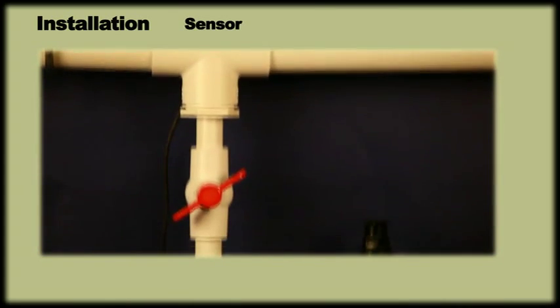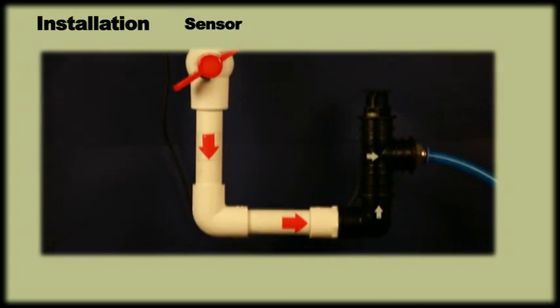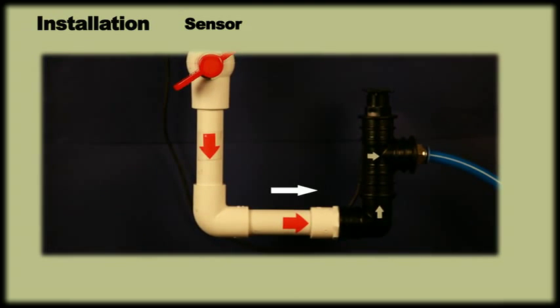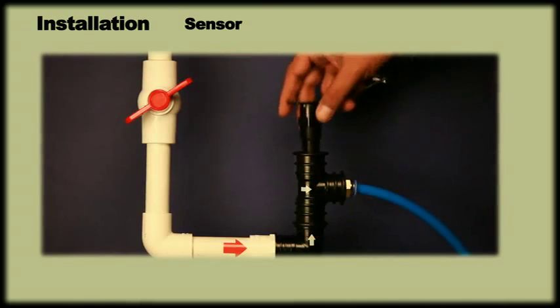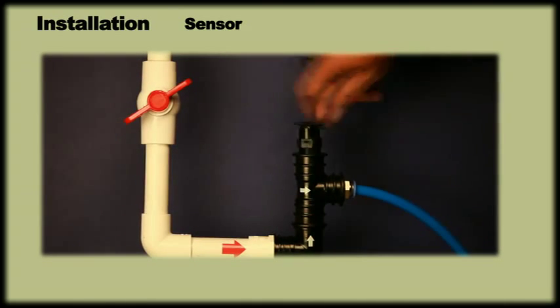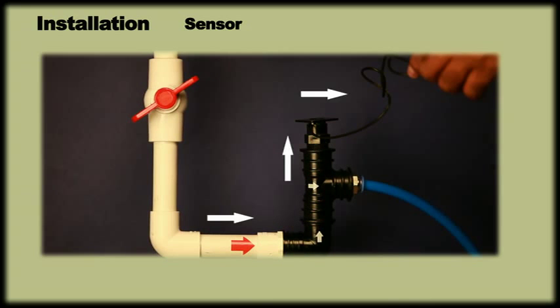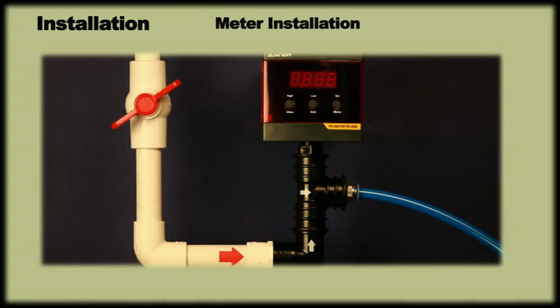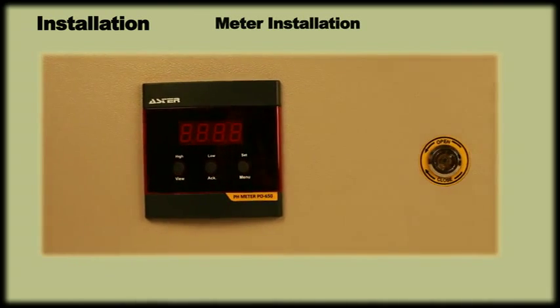The sensor should only be connected in the sampling line because the sensor body is not meant for a pressurized line. The sensor should always be mounted vertically in the pipeline. When the sensor is inserted into the sampling point, please ensure that the flow of water is from bottom to top. Meter installation. The meter is designed to suit both field and panel mount applications.